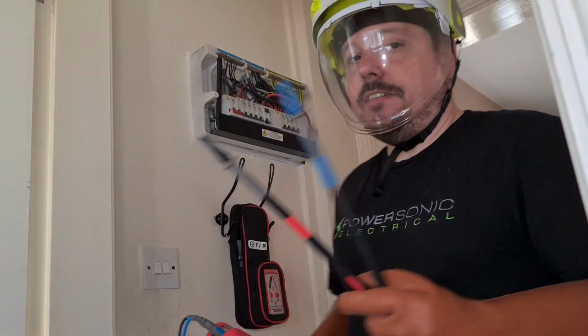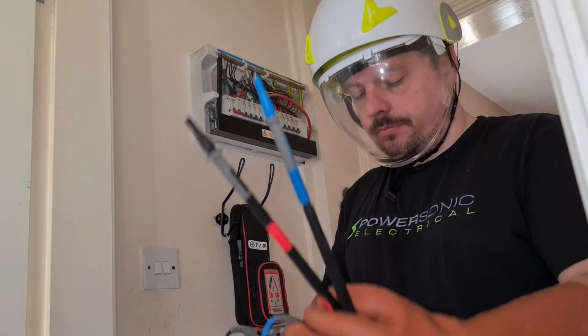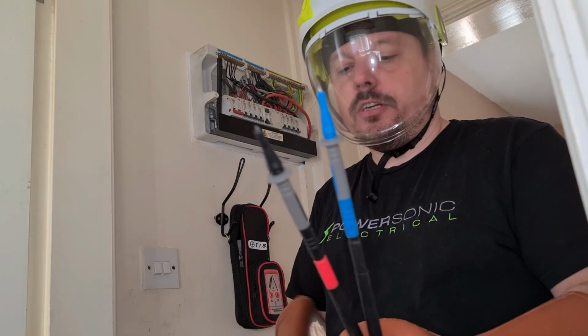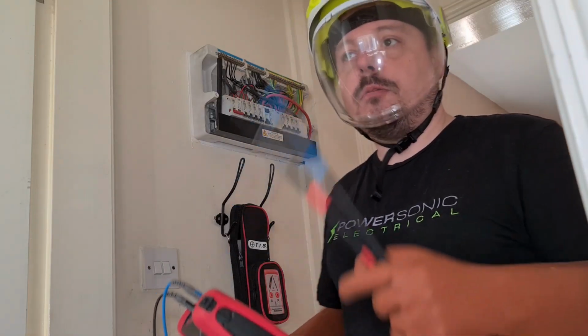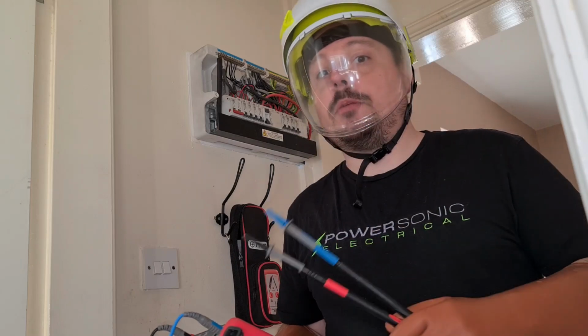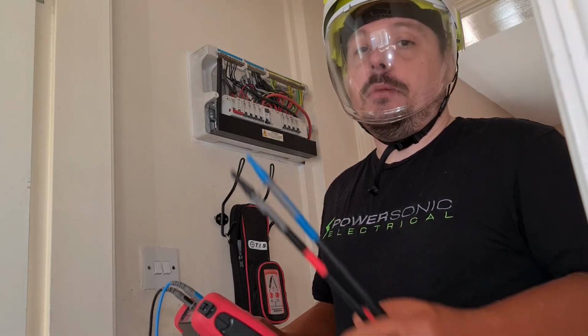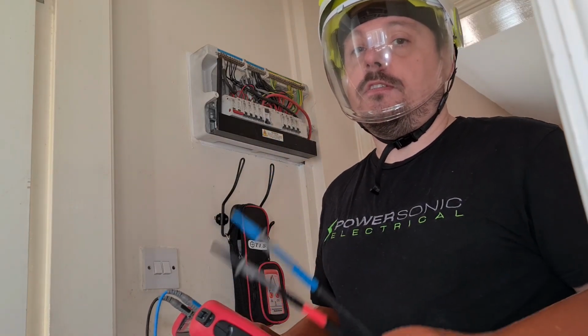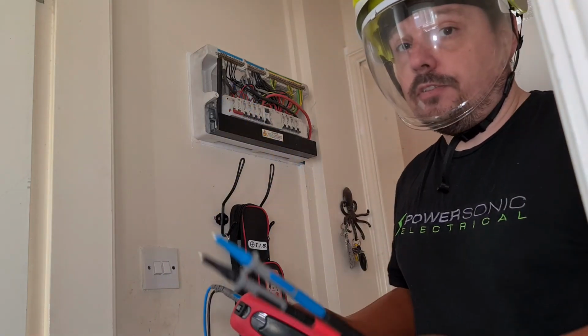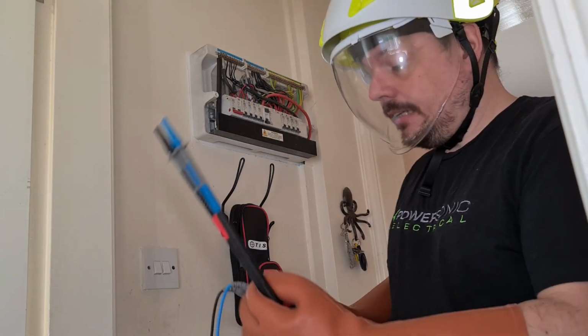So with this you'll see I've connected the main earth back up. When we're getting a measurement for your prospective fault current, prospective short circuit current, it needs to be with all the bonds and earths connected. So you're going to measure that highest value of current that could flow under fault conditions within an installation.